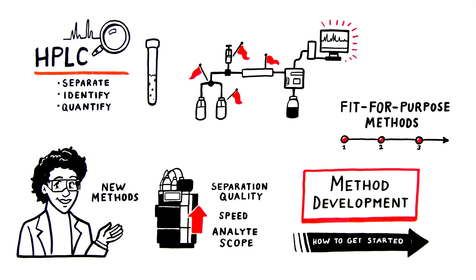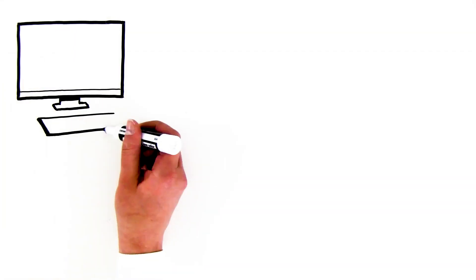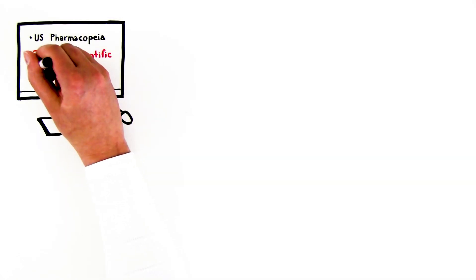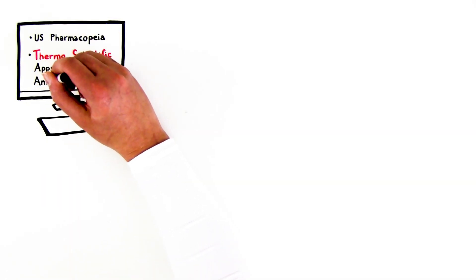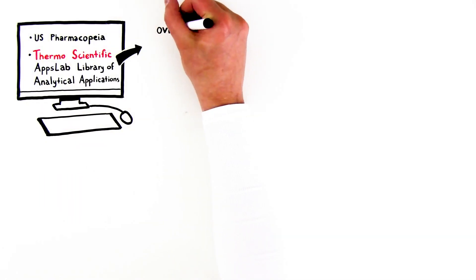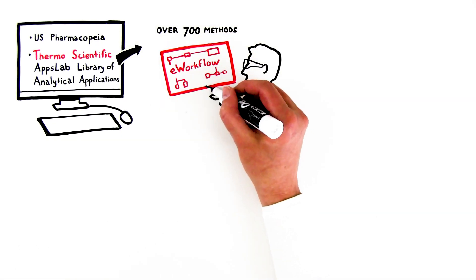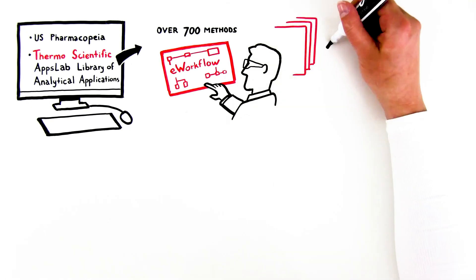Here's how to get started. First, ensure a suitable method doesn't already exist. The U.S. Pharmacopeia and Thermo Scientific Apps Lab Library of Analytical Applications, which contains over 700 methods of detailed e-workflow procedures, are good places to start.